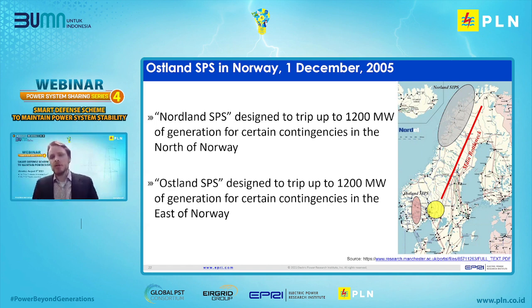In Norway in 2005, they have a number of system integrity protection schemes on their grid. 2 in particular, there's one in the north of the country, and for certain overloads, it trips up to 1.2 gigawatts of generators in the north of the country. There is also an SPS in the east of the country, which similarly monitors overload conditions and for certain contingencies will trip generators to prevent overloading of transmission lines.